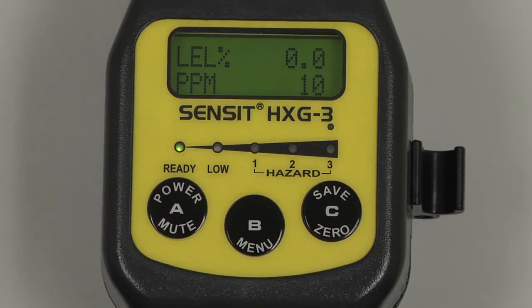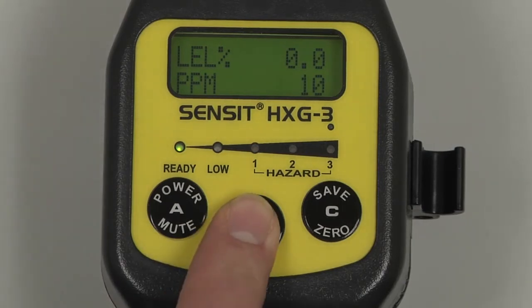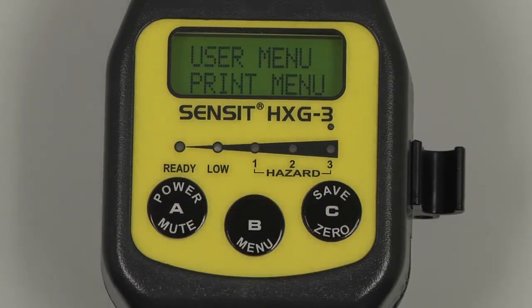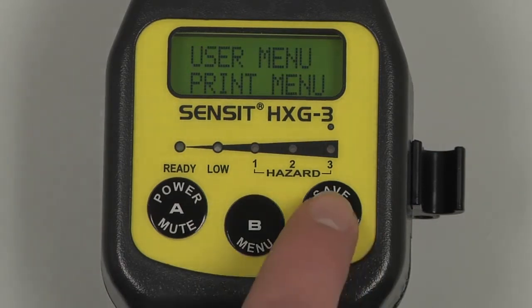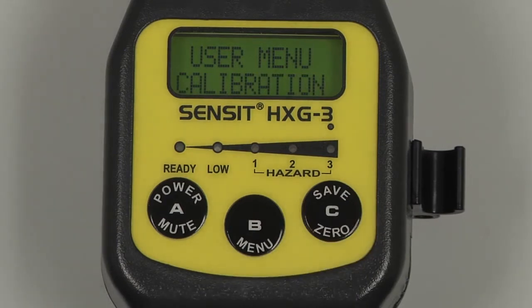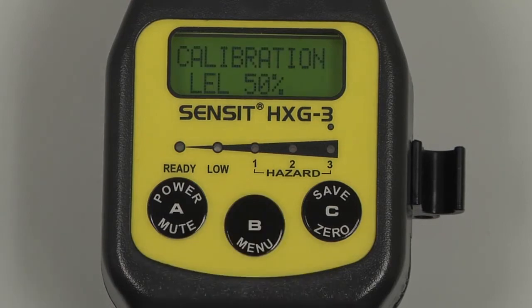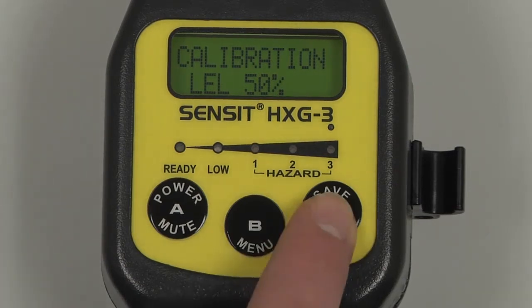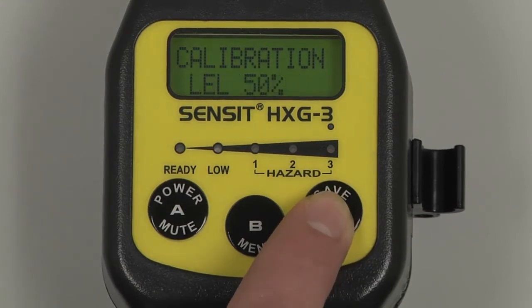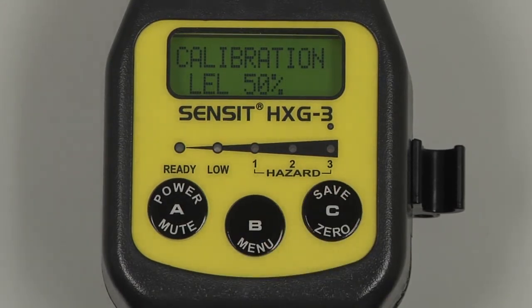To begin, enter into the user menu by pressing and holding the B button, and scroll through the menu by pressing and releasing the C button until calibration appears. Select by pressing and releasing the B button, and we will have a menu for the different possible calibration points. In this case, we only have 50% LEL methane, because that is how the instrument is set up.